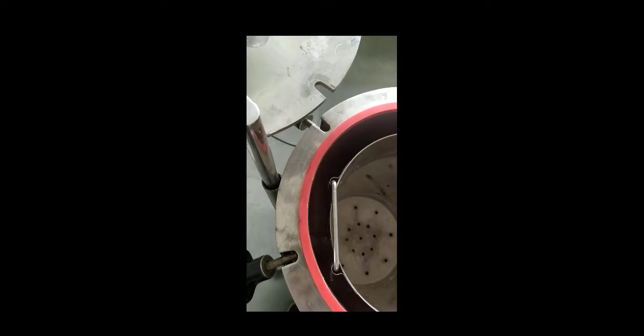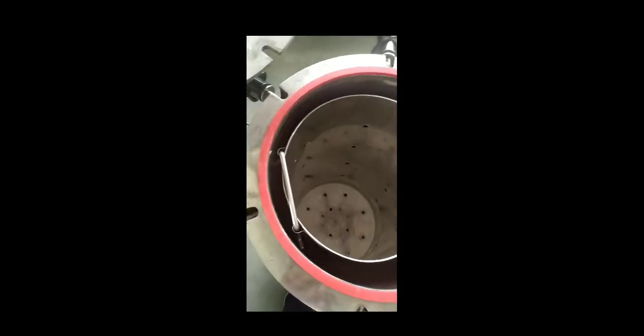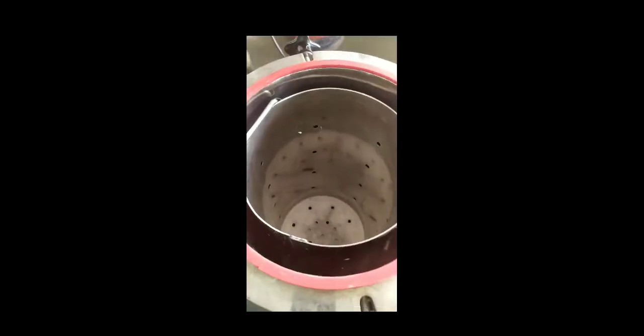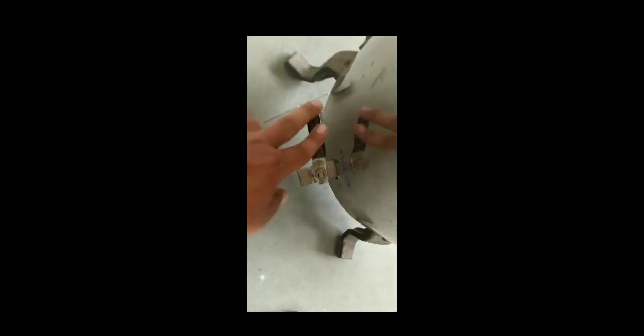This is the perforated basket, you can see there are various holes in it. At the bottom of this autoclave you can see the heating coil, and there is a stand which holds the basket and is also useful for maintaining the water level. We have to fill water up to this level, so the water does not touch the products or containers which have to be autoclaved. Put the basket, fill the water. If you have to remove that water after use, you can open this vent or this drain valve, so the water will be drained off.